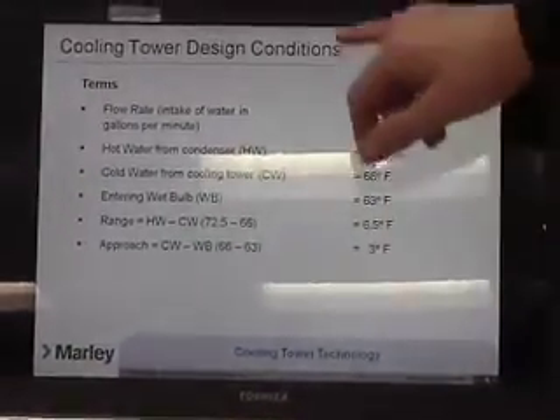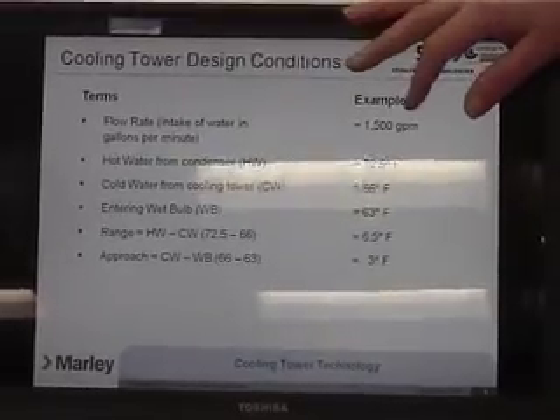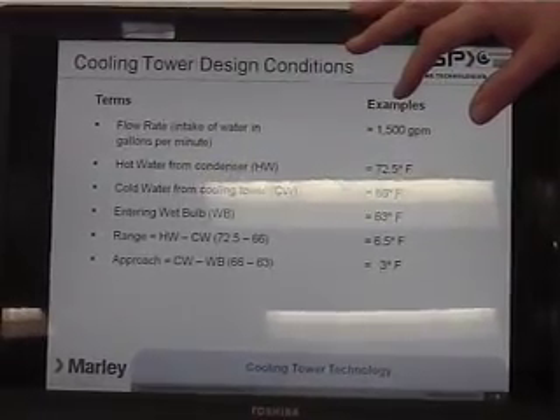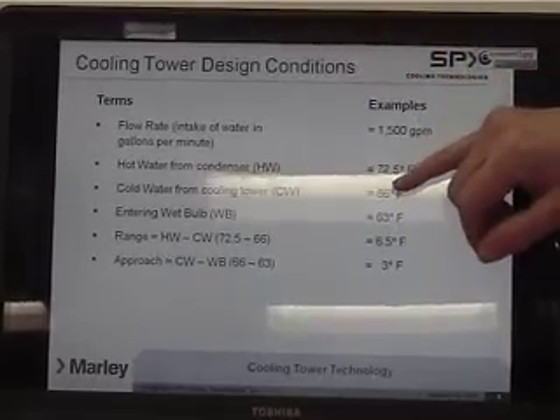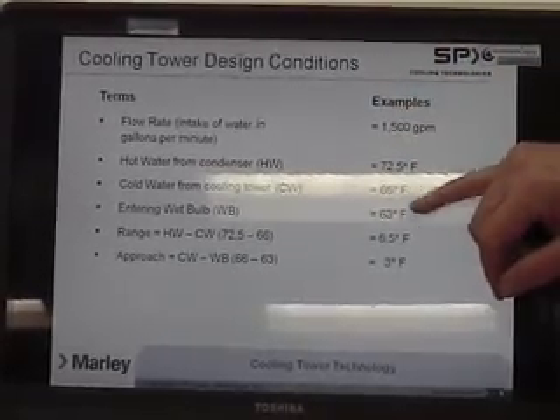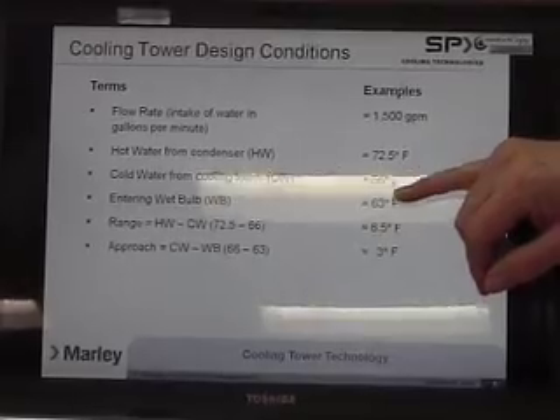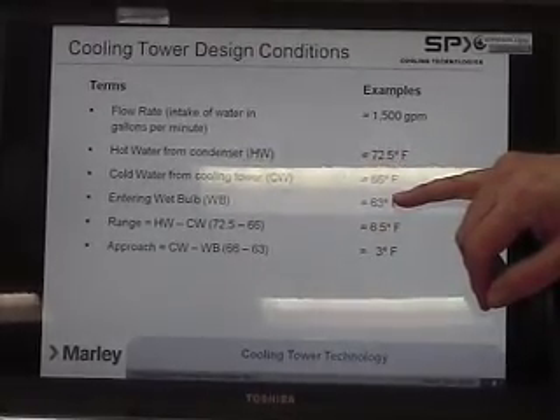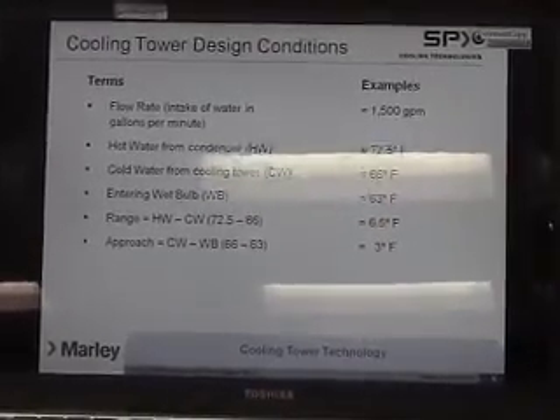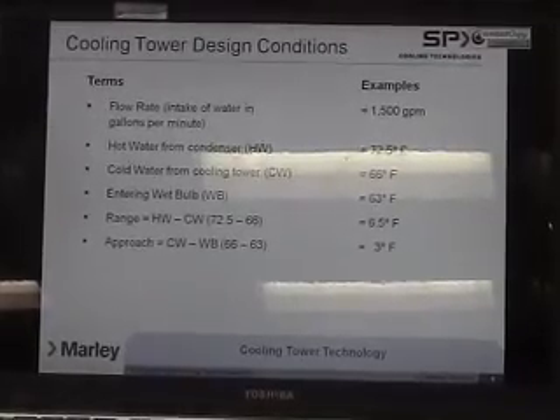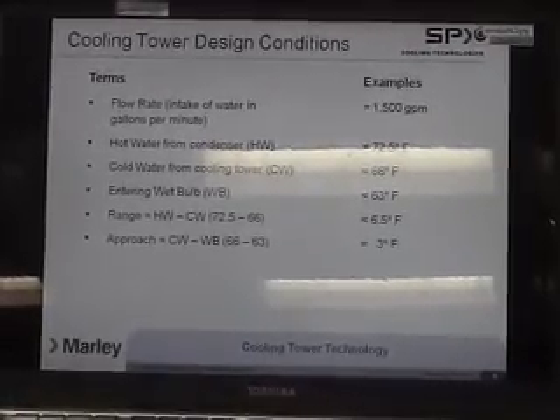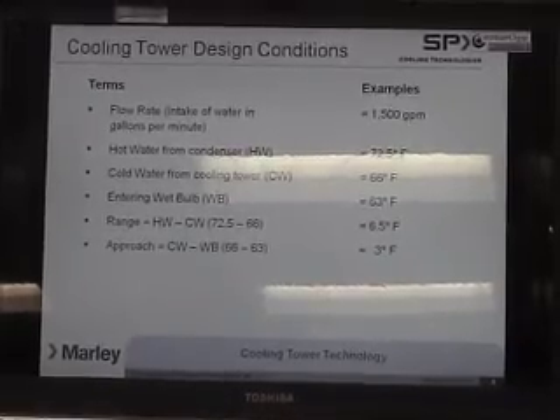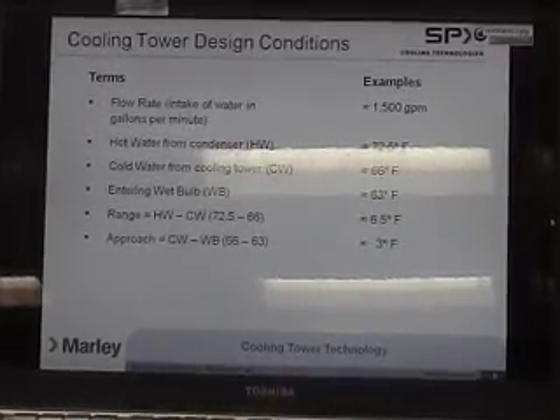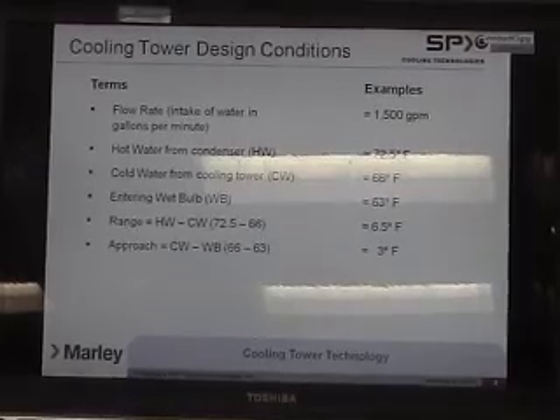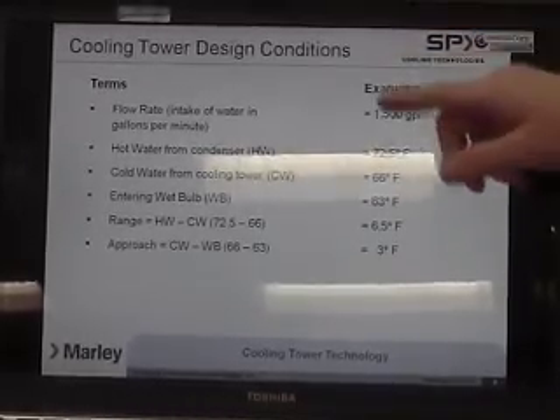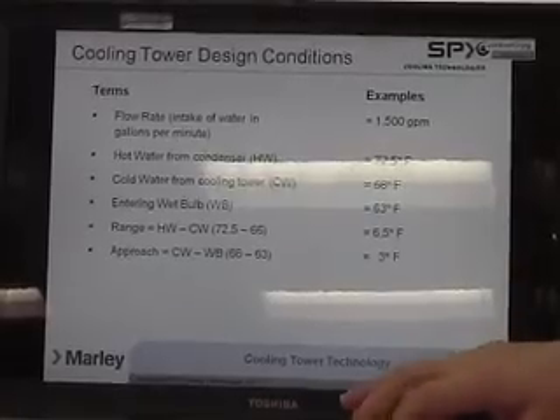This is actually the design conditions for your tower. It's designed to run about 1500 GPM, and the goal is to achieve a 66 degree cold water temperature at your 63 degree wet bulb. Wet bulb is the theoretical coldest water temperature your cold water could reach. It will probably never actually get to that cold water temperature, but the cooling tower will always try to get it to that cold water temperature.